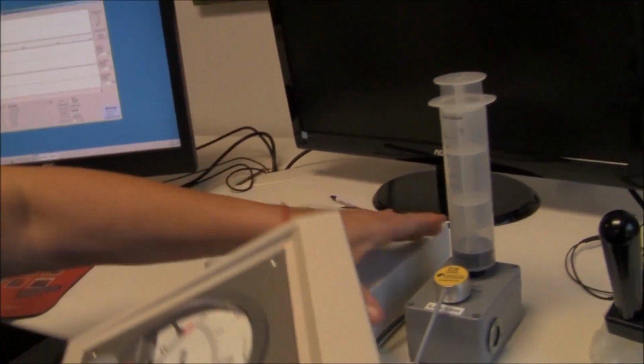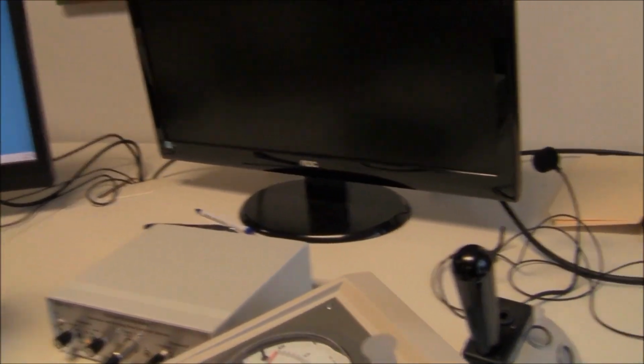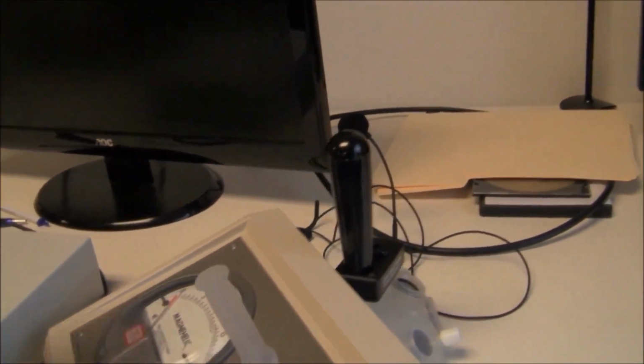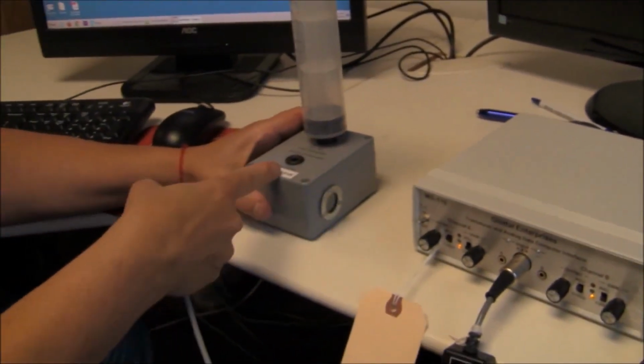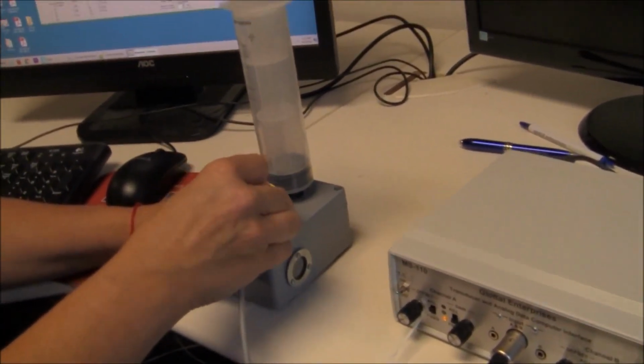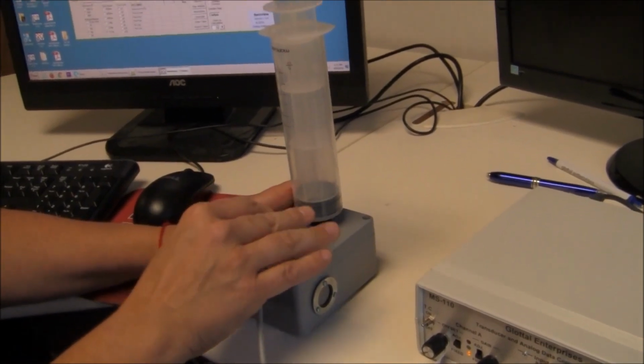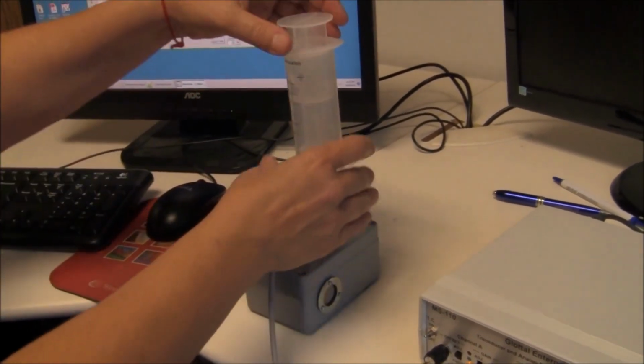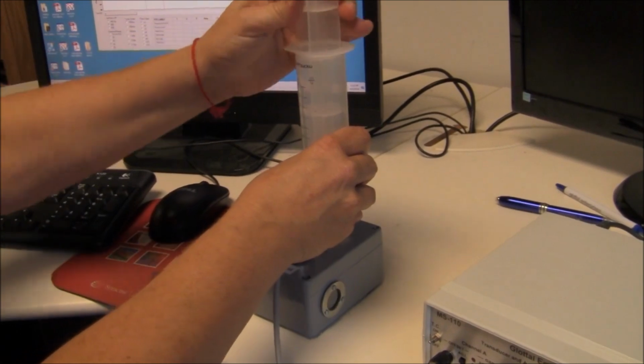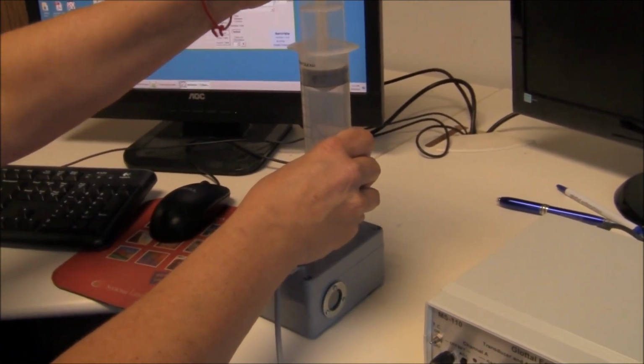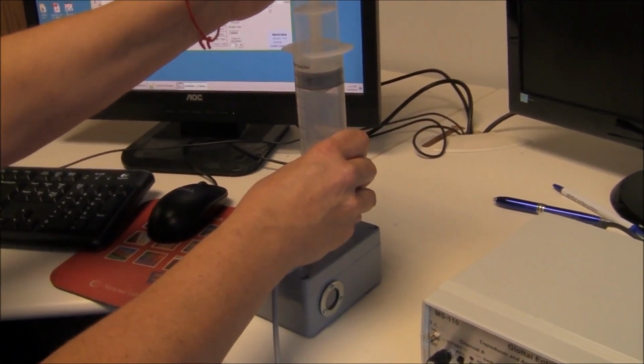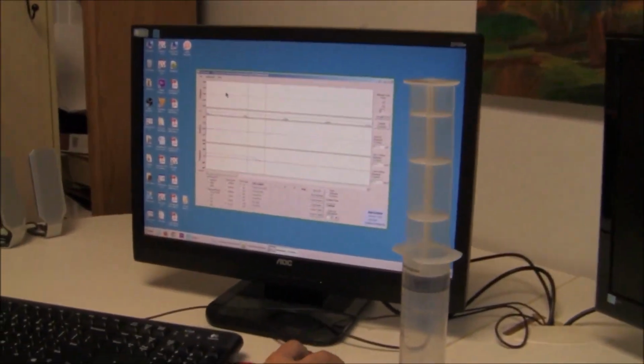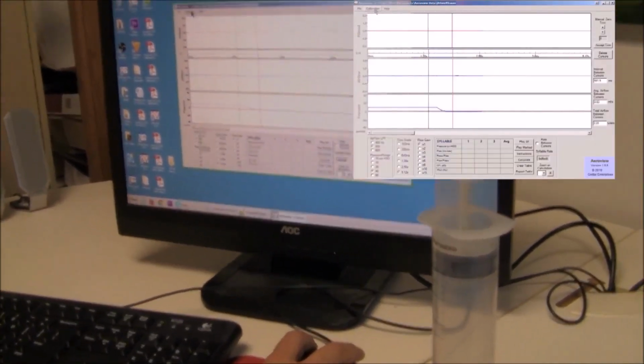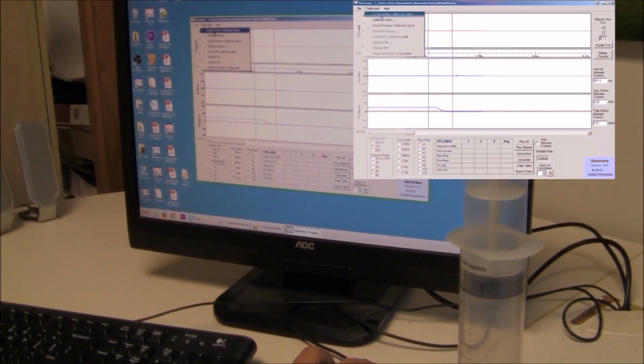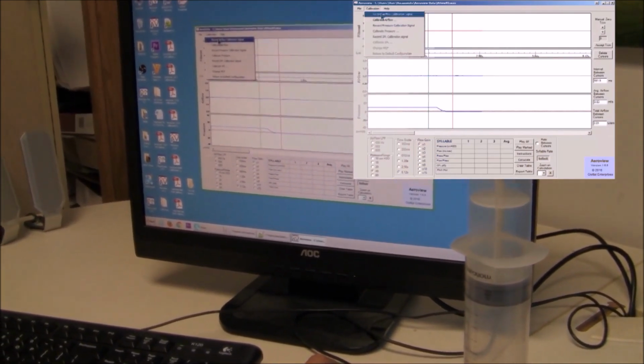Okay, so now we're going to bring over the airflow calibrator that has the PT2E plugged into the pressure port. This is the transducer port. We plug that in nice and firmly, and we are going to bring the syringe up to 140 milliliters. Okay, so we get that set. Now we're going to go back to the screen and press calibration, record airflow calibration signal.